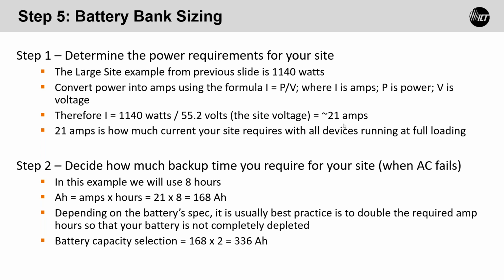So if we do this formula, we come up with 21 amps. And so 21 amps is how much current the site requires with all the devices running at full load, right? Which is not going to happen very often, but when we design a system, we're designing it to the worst case scenario. And then we need to decide how much backup time you require for your site. So let's use an average of 8 hours. So let's say a customer says, I need to have 8 hours of runtime. So we take the amps times the hours, so 21 times 8, that means 168 amp hours is what's going to be required to power this site with 1140 watts for 8 hours.